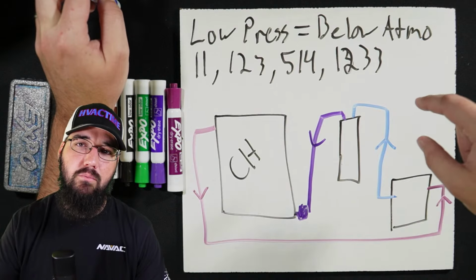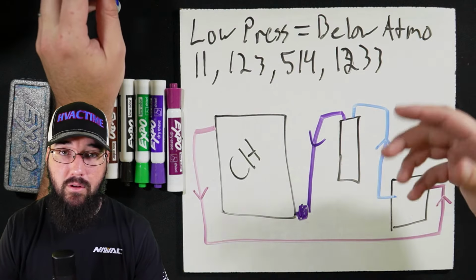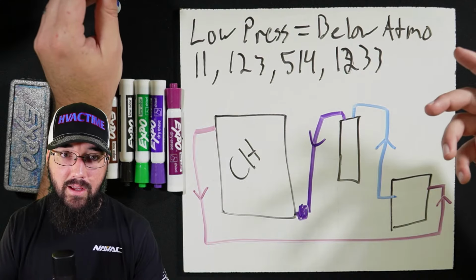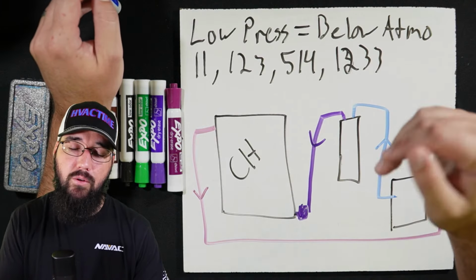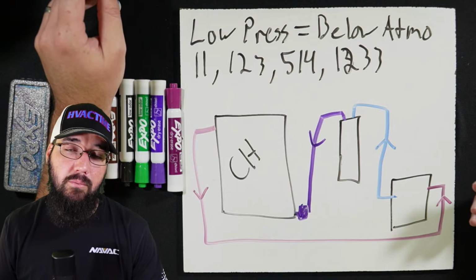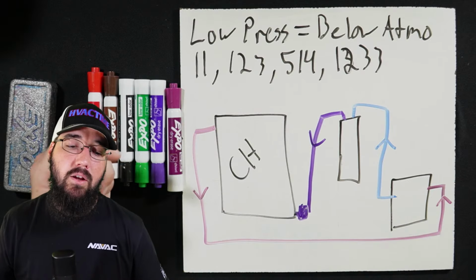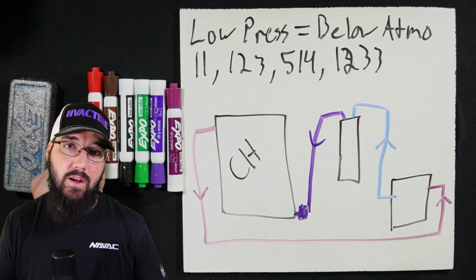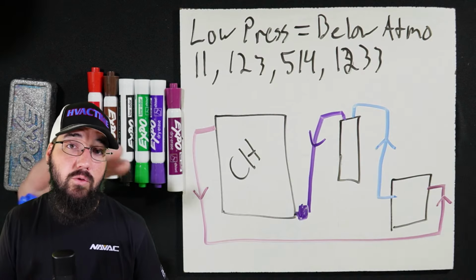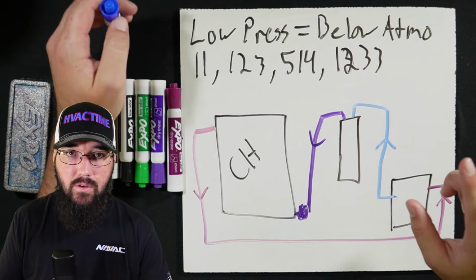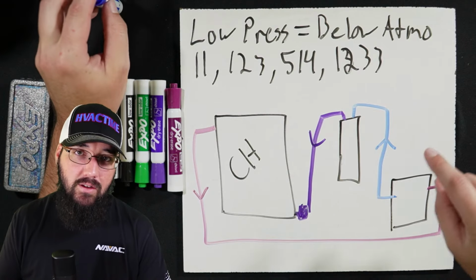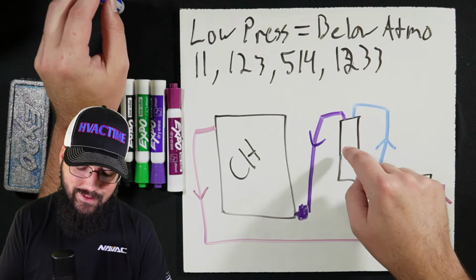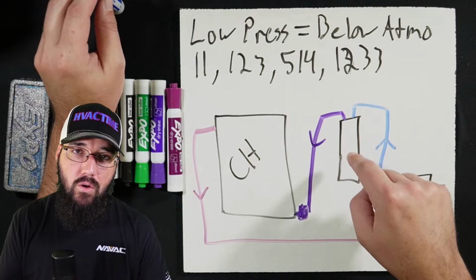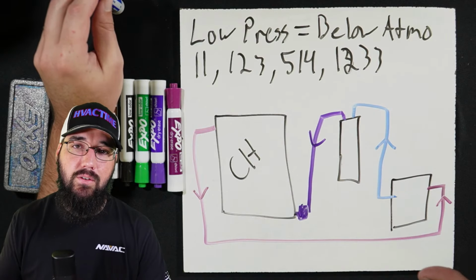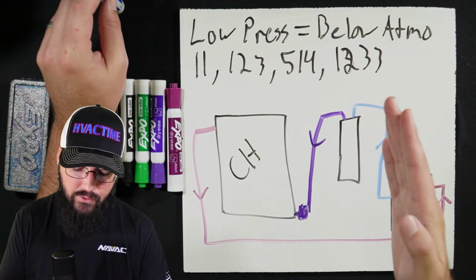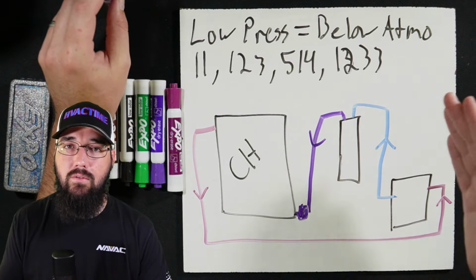You could try to hook up a pump and then just pump the liquid, whether it be through a recovery machine that's rated for that, like the NAVAC machines. You can move liquid through those. Or if you use a literal liquid pump. So they have liquid pumps on the market where they're not going to do anything for your vapor side, but they will transfer the liquid in between. So that is options. But I've tested a lot of these options, and it is not faster than the push-pull. Ultimately, the push-pull is your fastest process to get refrigerant from the tank into the machine and vice versa.